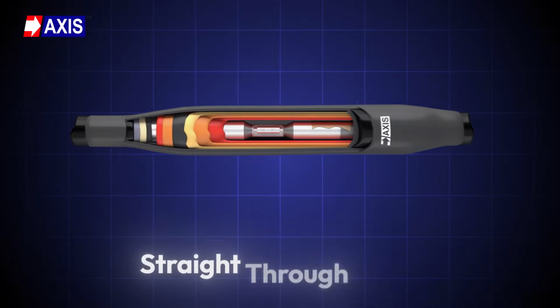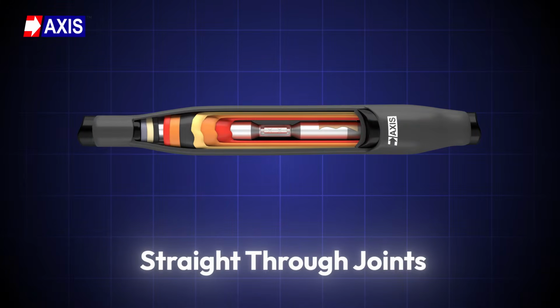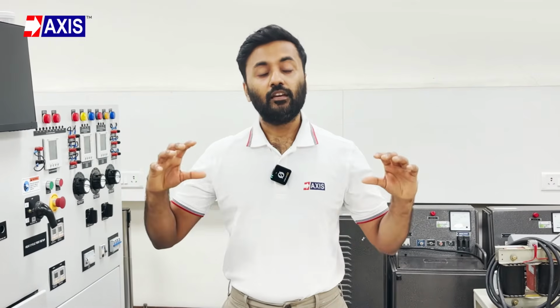Number 3. Straight through joints. These joints connect two cable segments, creating a continuous insulated link. They are designed for single and triple core cables operating from low to high voltage applications. They are made from cross-linked polyolefins so that they insulate against electrical faults and withstand the high temperatures of live cables. Once shrunk, they resist cracking, abrasion, and physical stress.